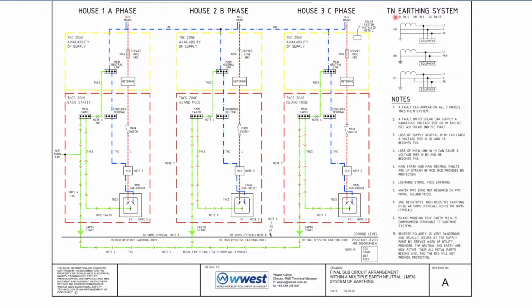Over here we can see that the earthing system that we use in Australia is a TN earthing system, and from that we have three different types of TN systems. Type A is this one here, a TNS. The beauty of this one is you've got your line active across the top coming out of your transformer, your neutral down here coming out, and then a separate protective earth down to your equipment. In type B, which is your TNC, from your transformer you've got your live active, then your neutral and your earth are combined, and that's what the C says, it's combined, so it's a PEN down to your equipment.